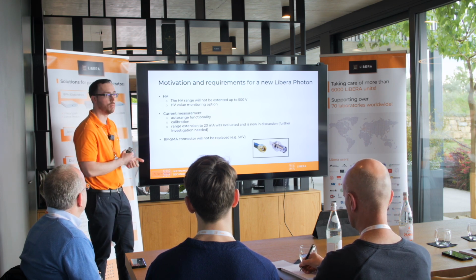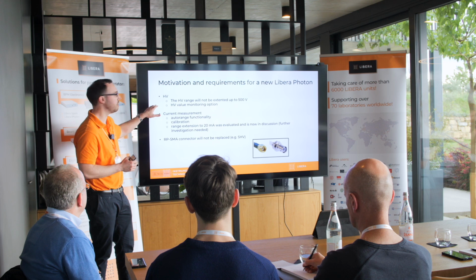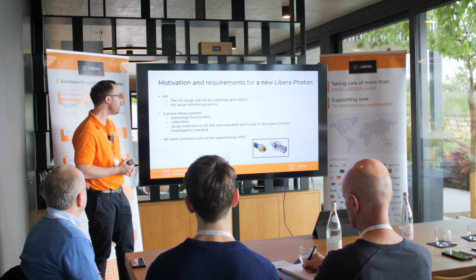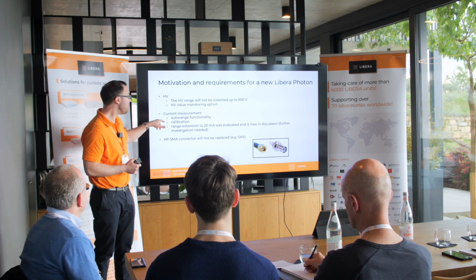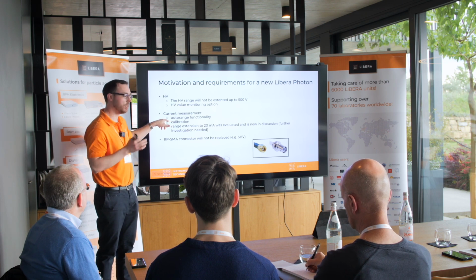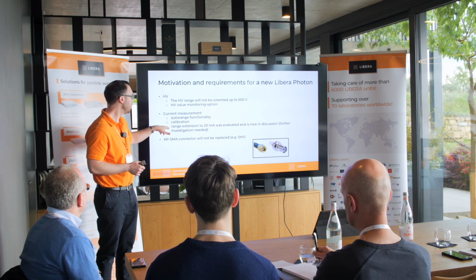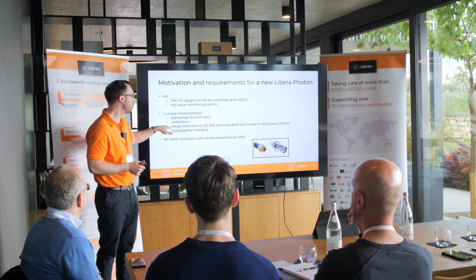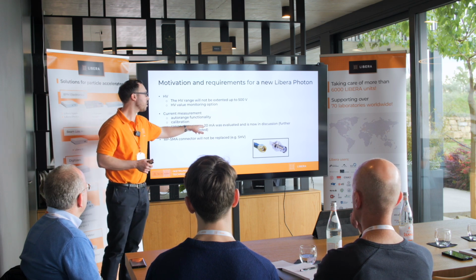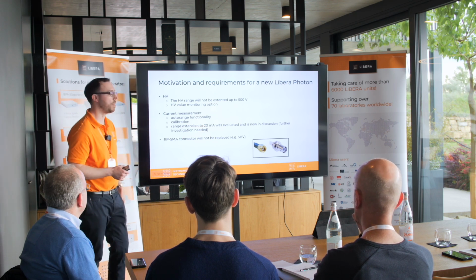About the current measurement functionalities, we will probably add the auto range, which is already done on the Libera current meter, which is somehow the cousin of the Libera Photon. The calibration, so to read out the data not in ADCs but in current values like picoamps. And then the hardware group is working to extend the range up to 20 milliampere.